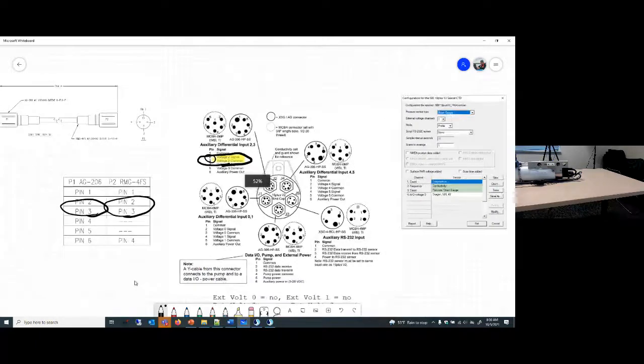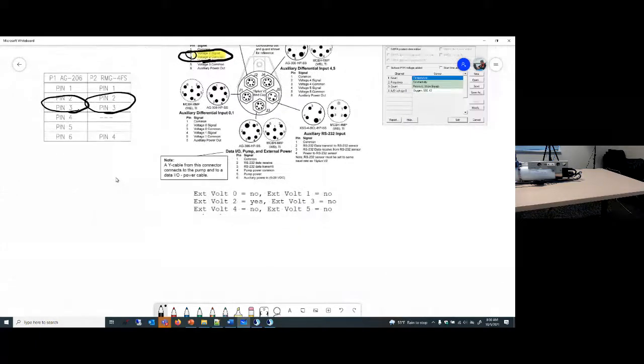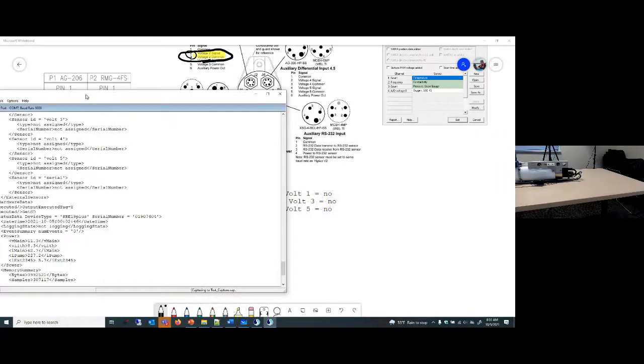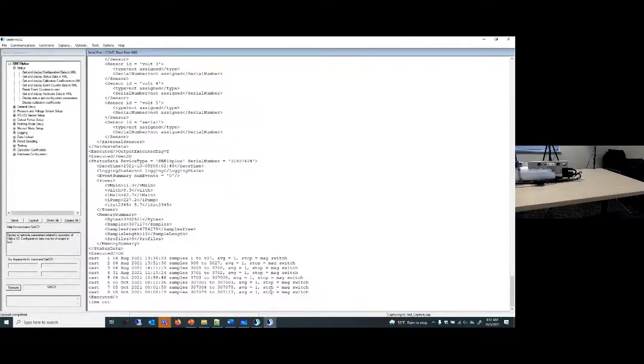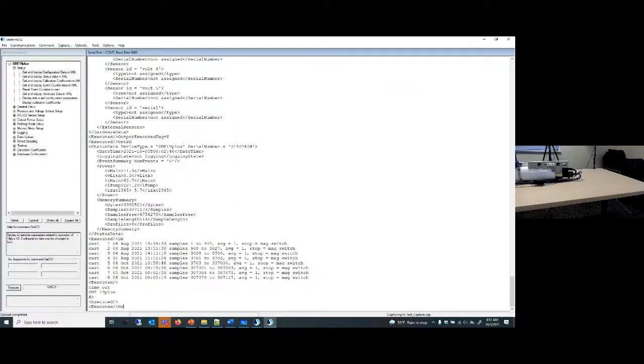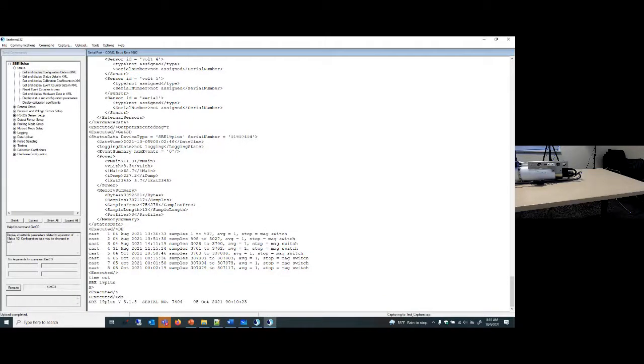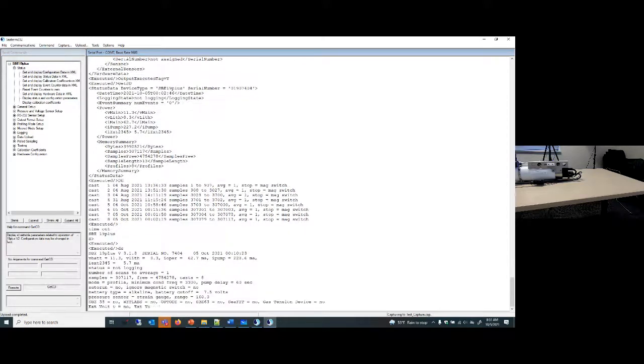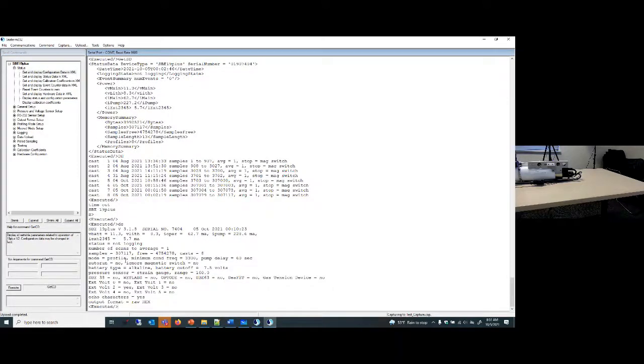So then what I'm going to want to do is go into CTerm and determine which voltage channel is currently connected. Now, I've pre-configured this CTD to already work with the oxygen sensor, but when I send the DS command, I see external volt 0 is no, 1 is no, 2 is yes, 3, 4, and 5 are all no. So this is already configured to accept data from my oxygen sensor.